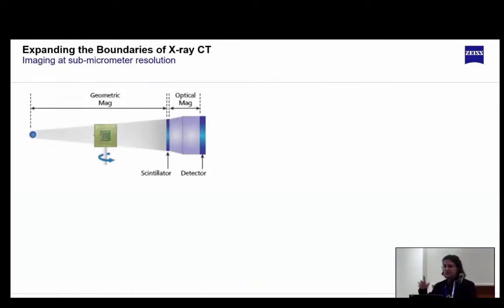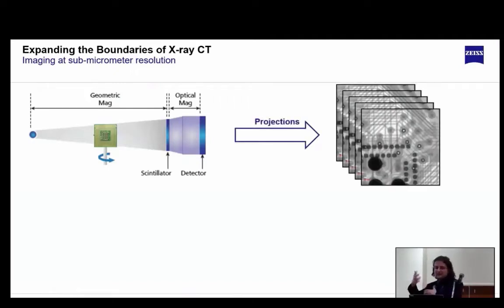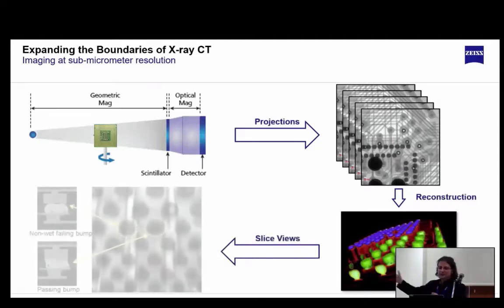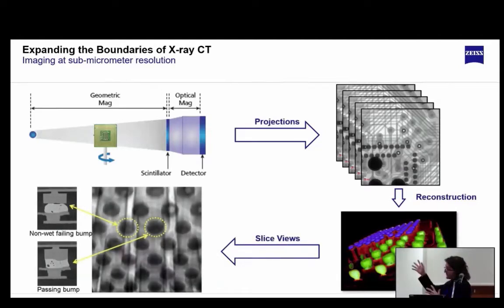In practice, the measurement workflow is composed of 3 basic steps. First, an operator selects the best settings for scanning the part based on the geometry, size, and composition. And then the X-ray system rotates 360 or 180 degrees and starts collecting snapshots or image projections at different angular orientations. After collecting several projections at those angular positions, a software reconstruction will generate a 3-dimensional model of the part volume. And this can be used to non-destructively inspect or do quality control of several types of applications from inside of the device.